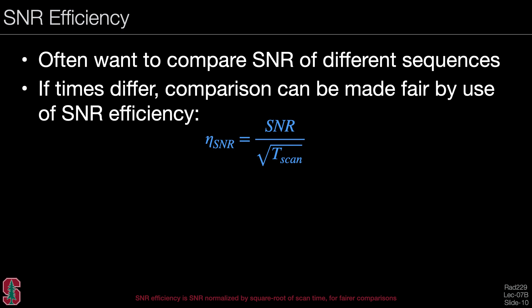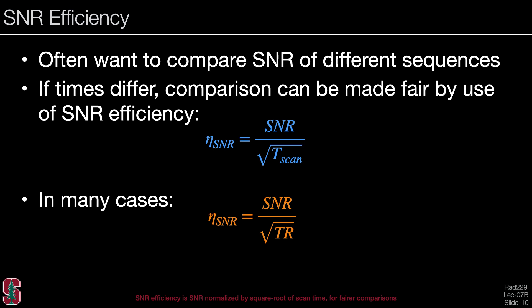Now let's talk about SNR efficiency. We often want to compare the SNR of different sequences that may have different parameters. If the scan times differ, we can normalize the comparison using SNR efficiency, defined as eta_SNR equals SNR divided by the square root of the total scan time. In many cases the total scan time is proportional to TR, so this efficiency can often be written as SNR divided by the square root of TR — though you should be careful applying this across different sequences.